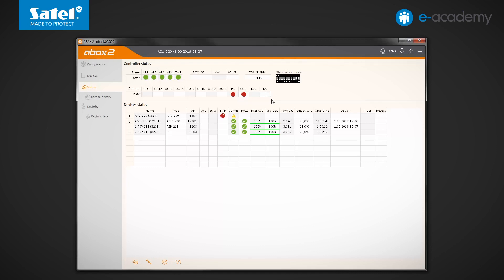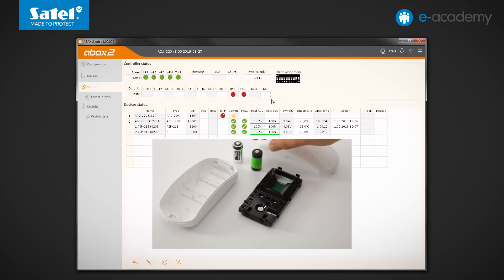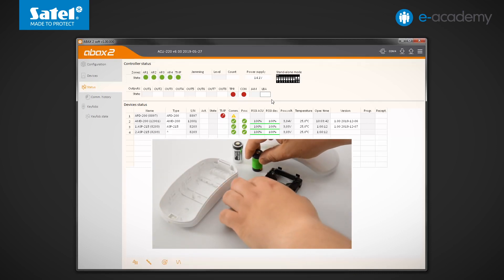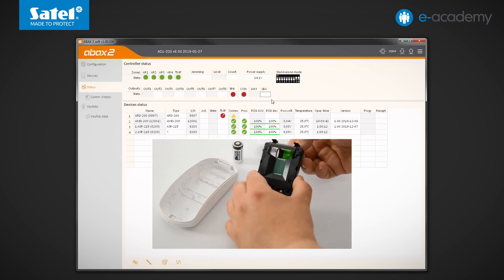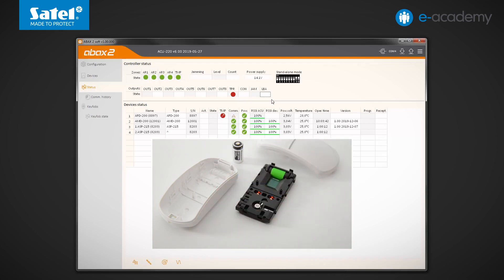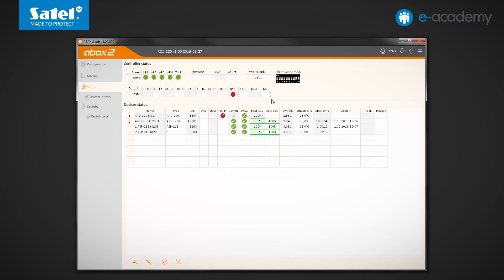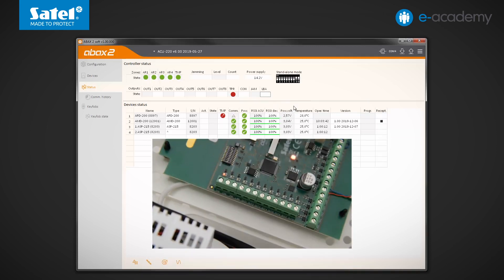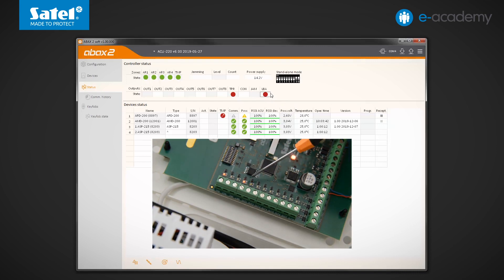Now, to test the operation of the LBA output, let's install a low battery in the APD200 detector. The detector has connected to the system. As you can see, the measured value of its battery voltage is low. After a while, the LBA output status changed to active.